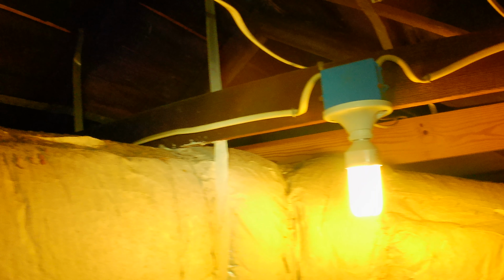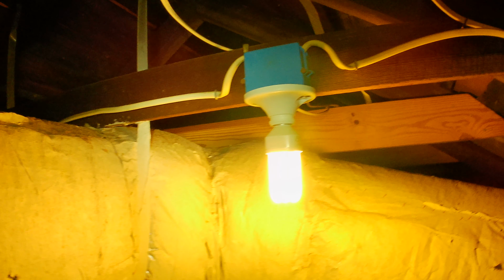So what I have learned, and most manufacturers recommend, is to have a dedicated circuit breaker for any of these HVAC systems. So we will recommend to hire an electrician and make this furnace independent of everything else. So right now we're testing, like I said, static pressure and amp draw for the inducer fan motor.